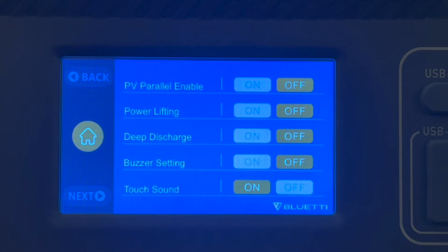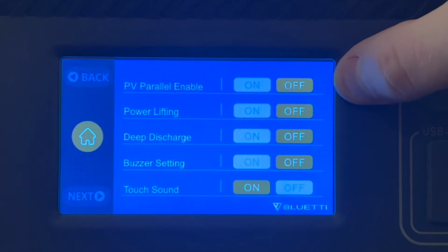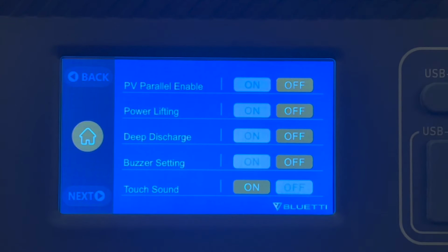You can, in theory, also run two solar arrays to the device using a MC4Y cable. Take the same solar array up to both inputs, but be very, very careful with that. On the AC300s, it's less of an issue. On the AC500, the problem is that the MC4 connectors are only rated for 20 amps, and you can pull 30 amps on this device. So you've got to be real careful not to overload your connectors, or you're going to have hot and/or melting wires. So if you are going to use a single run with PV parallel, don't overload it.